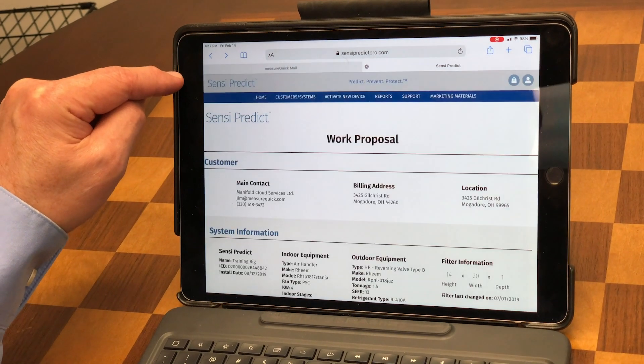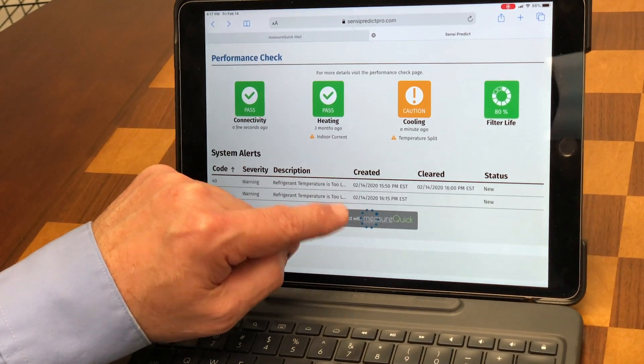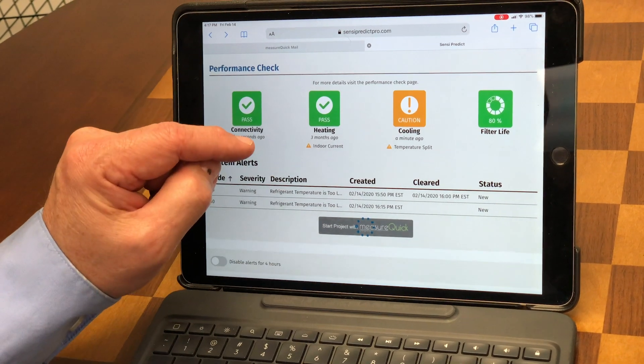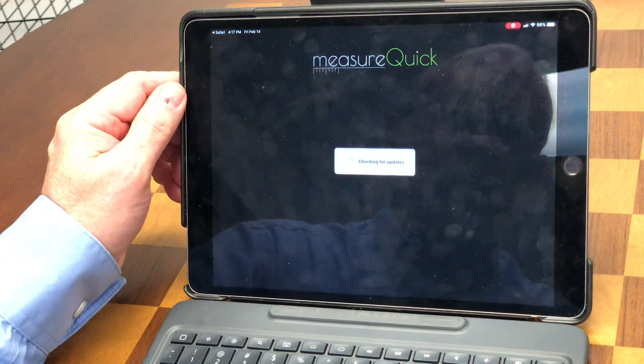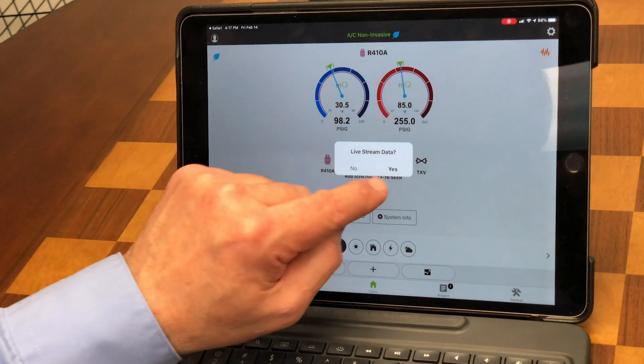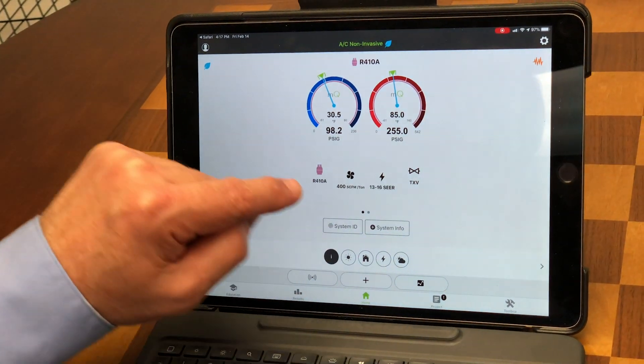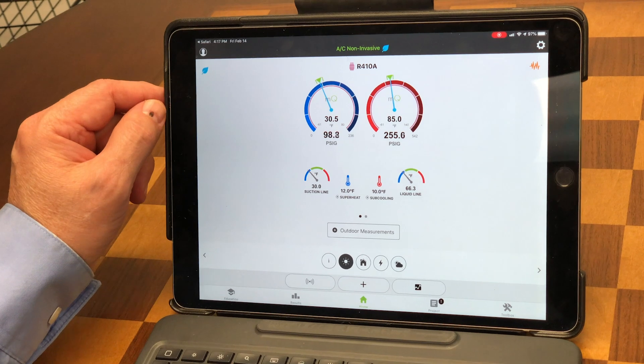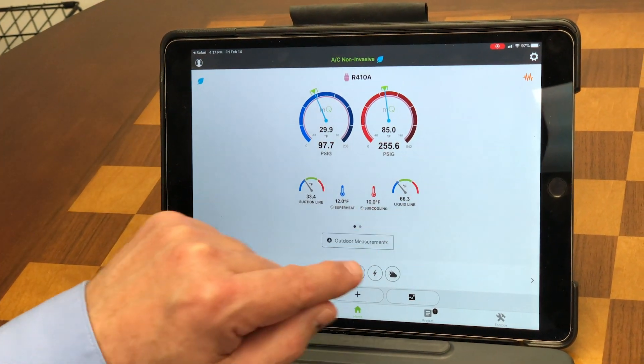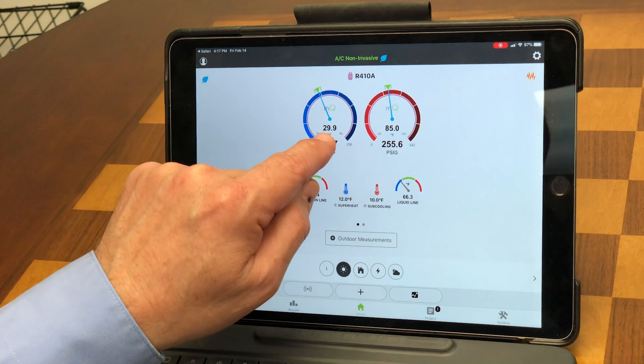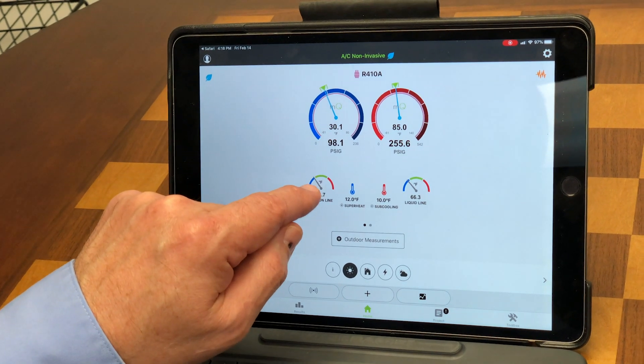We'll go back and open this up in MeasureQuick — it will say 'starting a project with MeasureQuick.' This is really nice because a lot of technicians are used to this way of looking at it. It checks for updates and then asks for the live stream data. I hit yes and then open, and it's live streaming data into MeasureQuick. I can see my suction line temperature is low, my liquid line temperature is low, and my coil is operating below freezing.